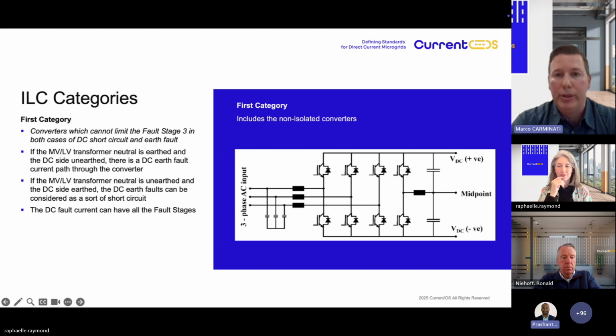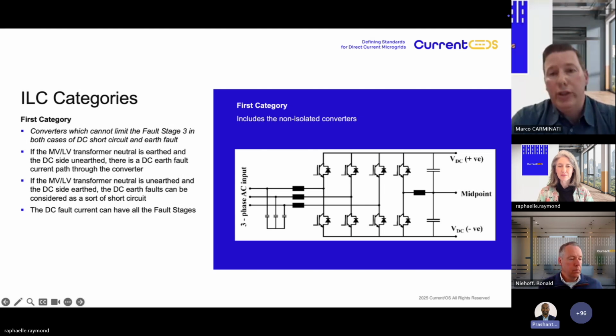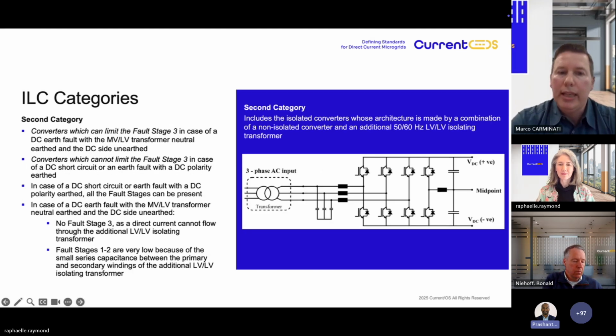Another story if we connect the midpoint directly to the neutral point of the transformer. So in this case, the fault current can have all the fault stages according to the ratio between the inductances and the DC capacitor. The second category includes the so-called isolated converter, but having an architecture made by a combination of a non-isolated converter, as we have seen in the first category, plus an additional 50 or 60 Hertz low voltage isolating transformer that you can see in this picture. It is not the medium voltage low voltage transformer, usually it is another one.